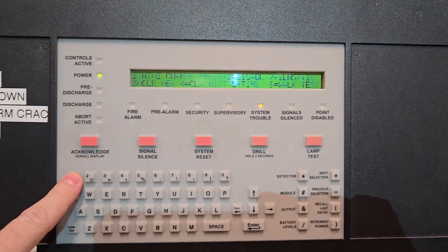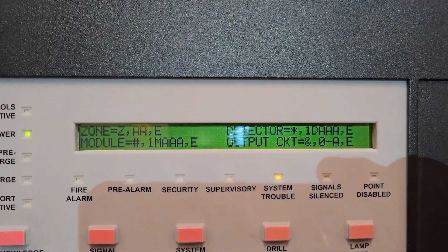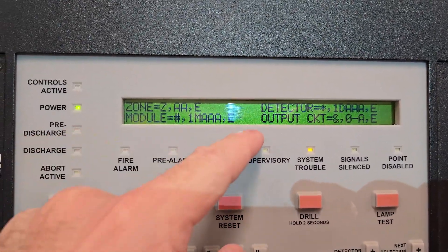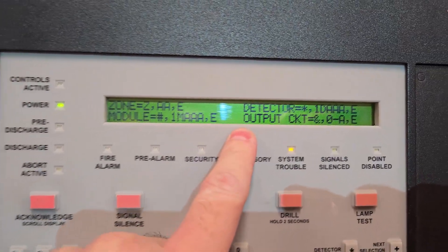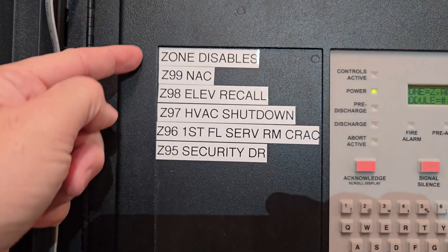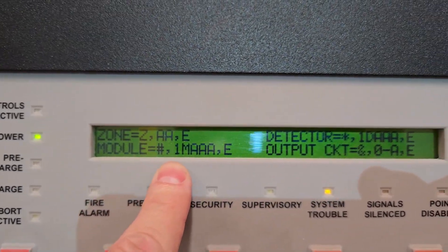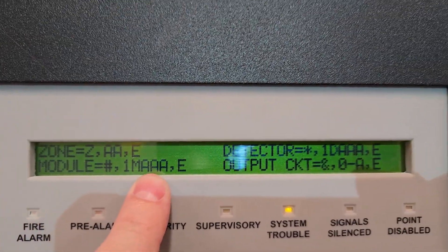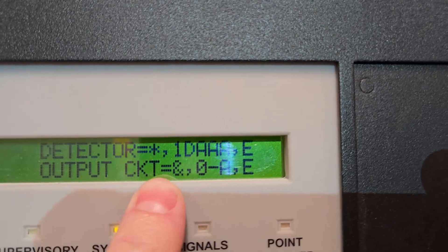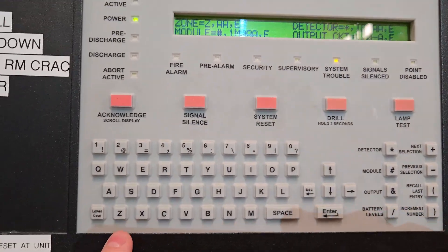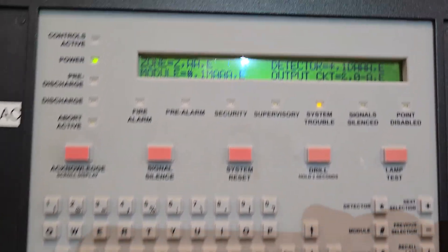I hit number one and now it asks how I want to disable: by zone, by module, by detector, or by output. For zones — they all start with Z on this panel — to disable a zone you hit Z then the numbers. For module you hit the pound sign then the numbers. For detectors you hit the star then the numbers. For output you hit the ampersand symbol then the numbers.